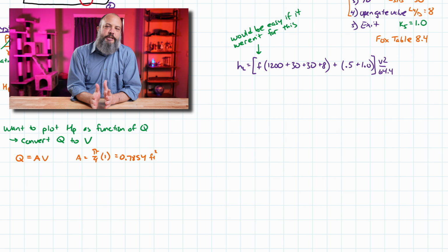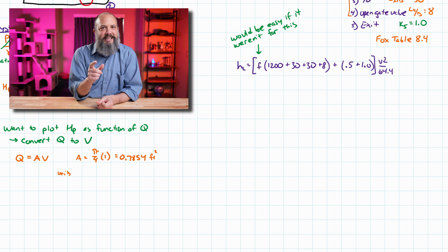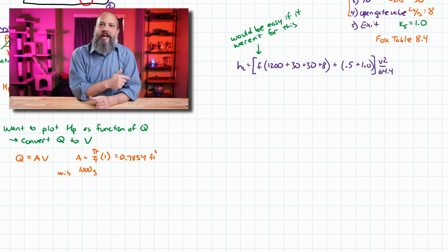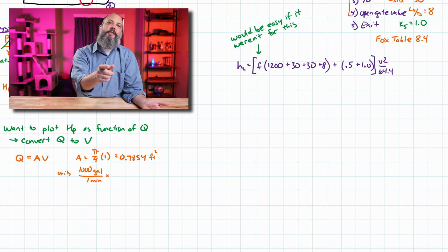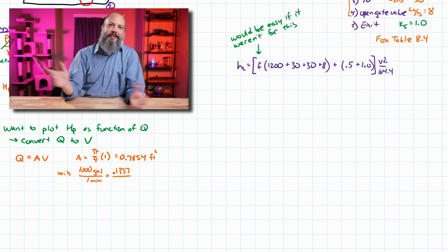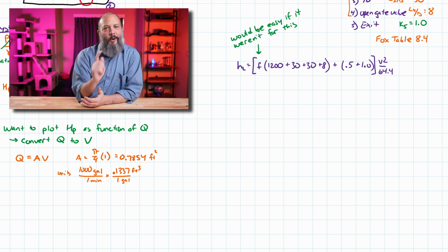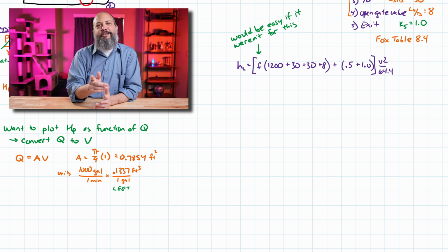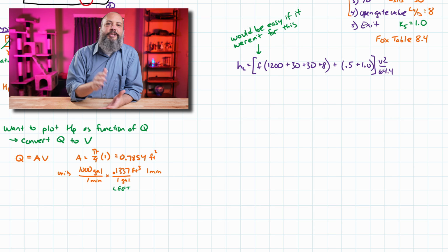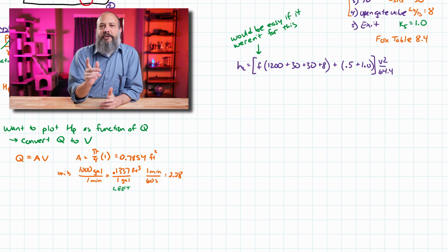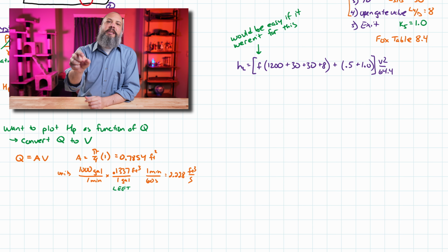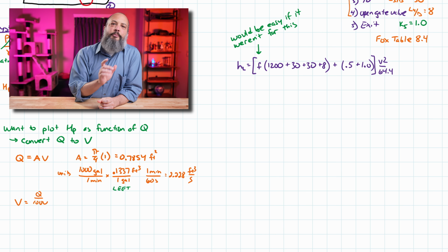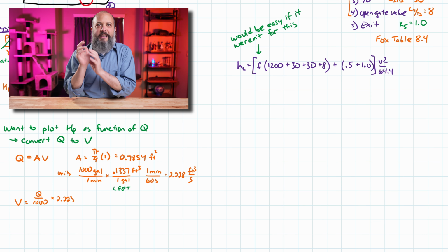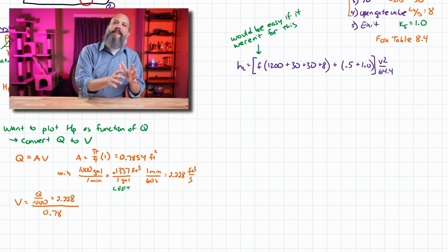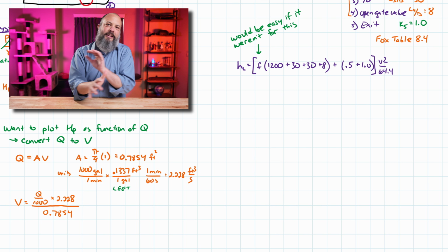But we're also going to have to convert the units. We want velocity in feet per second, but Q is in gallons per minute. So we're going to use the best conversion factor ever, that I never forget. Any gamer out there should always remember how to convert gallons to feet cubed, because it's LEET: 0.1337 feet cubed is 1 gallon. Once you see it, you'll never forget it, right? And 1 minute is 60 seconds. So we get a conversion here, 2.228 feet cubed per second for Q. So to get V from Q, we take Q divided by 1,000 times 2.228 divided by 0.7854. That converts Q from gallons per minute to V in feet per second, both from the equation for V and the unit conversion all in one.